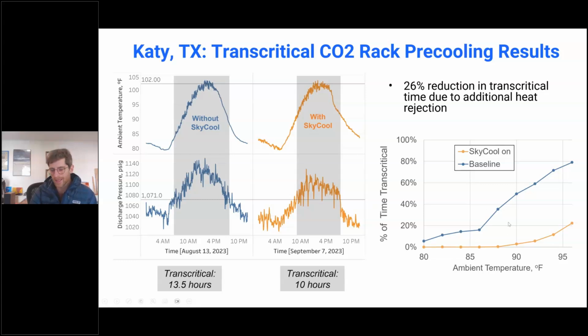And so what we did is we binned that data over the year, over the summer specifically, to show a reduction in these transcritical hours. So when it's really hot outside, we're still seeing transcritical behavior with our system, but certainly far fewer hours than you would have otherwise. In this particular site, since these are adiabatic condensers, we're not necessarily saving water. The spraying is happening at the same frequency and same rate with our system on versus off. But the benefit of having our panels there is that the refrigerant can get closer to the wet bulb, and so that's reducing the number of these transcritical hours and then saving energy and power.